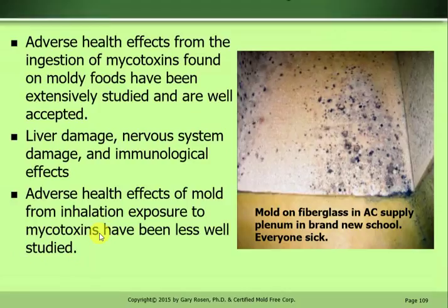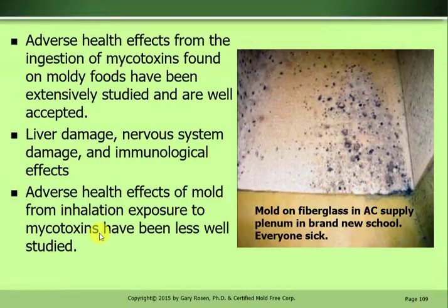Health effects of mycotoxins. Adverse health effects from the ingestion of mycotoxins found on moldy foods have been extensively studied and are well accepted: liver damage, nervous system damage, and immunological effects. Adverse health effects of mold from inhalation exposure to mycotoxins have been less well studied. This picture right here shows mold on fiberglass in an AC supply plenum in a brand new school, which turns out that everyone was sick.